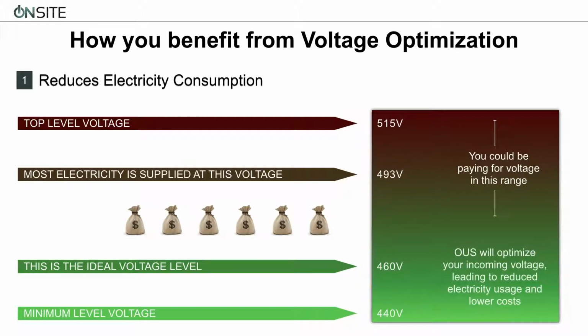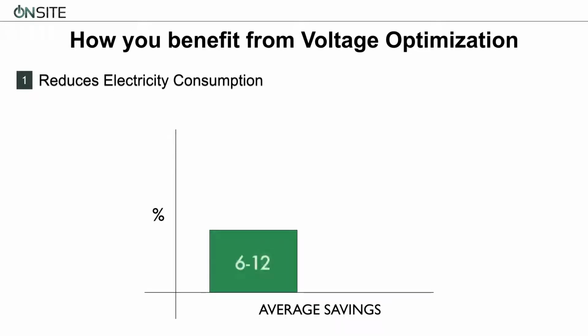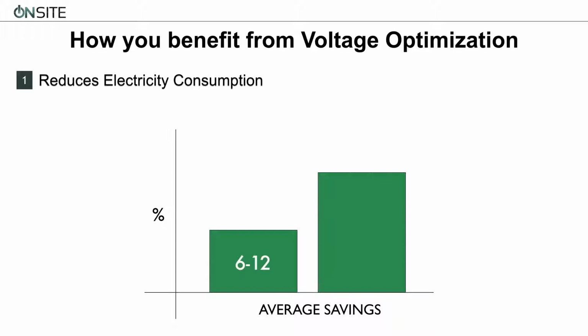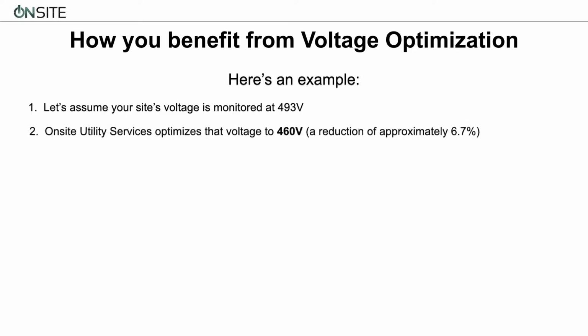Onsite Utility Services can manage your incoming voltage and lower your costs. As a matter of fact, the average savings with voltage optimization ranges between 6 and 12%, and we've even seen savings as high as 21%. Here's an example. Let's assume your site's voltage is monitored at 493 volts, which would be about average. Onsite Utility Services lowers that voltage to the optimum level of 460 volts, representing a reduction of approximately 6.7%.